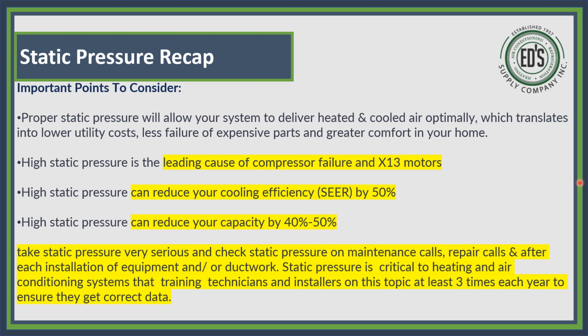445 CFMs. What that means is I just reduced my capacity between 40 and 50% because my static pressure was off. So now in heat mode, I just had 1 ton of air in that house. No wonder they were complaining. And then they had a 5 kW heat kit, so it was only producing 64-degree air. So now you can see why the homeowner was upset. So what can you do at that point? Because there's not a tap for heat to go into that 5.